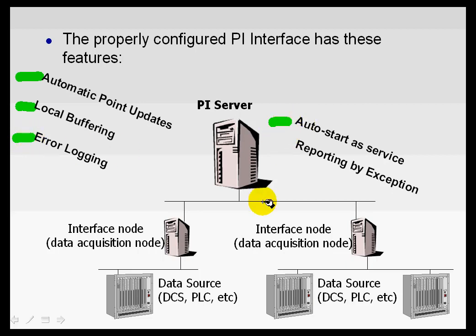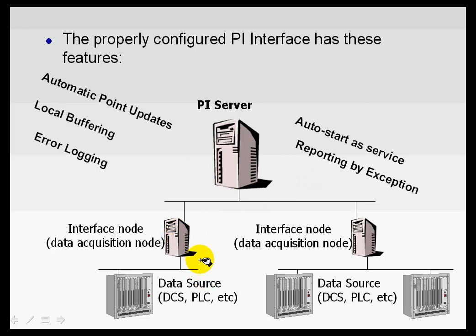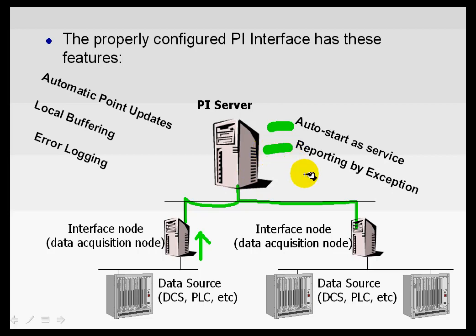We'd like the interface to automatically start up as a service. On the day that the entire network goes down and everything comes back up, when the interface node is back up and running, you would like it to inquire of the server, 'Are you there?' — and then start sending data as soon as it can. So we want automatic startup after reboot. We also would like to report by exception, meaning we only want to receive new data when that data has changed significantly from the previous values. That's what we mean by reporting by exception, or exception testing.